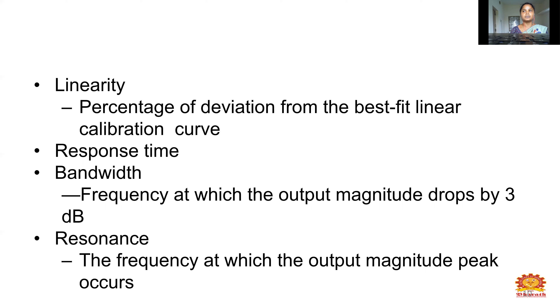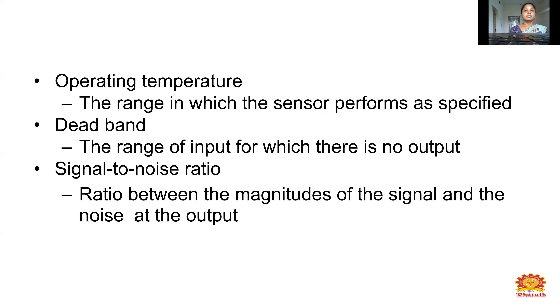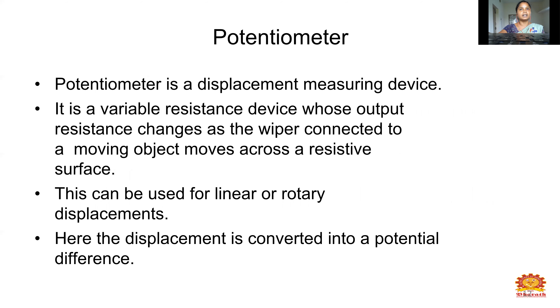Next is response time bandwidth — the frequency at which the output magnitude drops by 3 dB. Resonance is the frequency at which the output magnitude peak occurs. Operating temperature is the range in which the sensor performance has specified values. Dead band is the range of input for which there is no output. Signal-to-noise ratio (SNR) is the ratio between the magnitudes of the signal and the noise at the output.